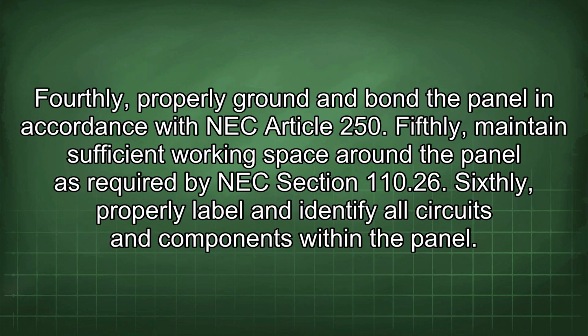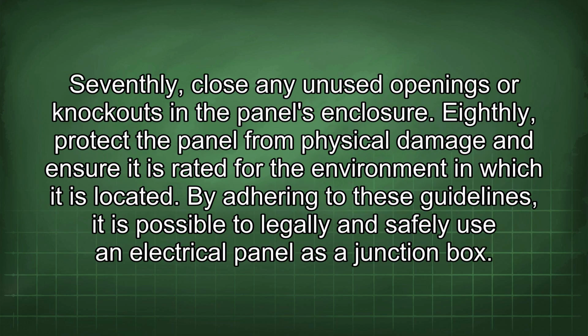Fourthly, properly ground and bond the panel in accordance with NEC Article 250. Fifthly, maintain sufficient working space around the panel as required by NEC Section 110.26. Sixthly, properly label and identify all circuits and components within the panel. Seventhly, close any unused openings or knockouts in the panel's enclosure. Eighthly, protect the panel from physical damage and ensure it is rated for the environment in which it is located.